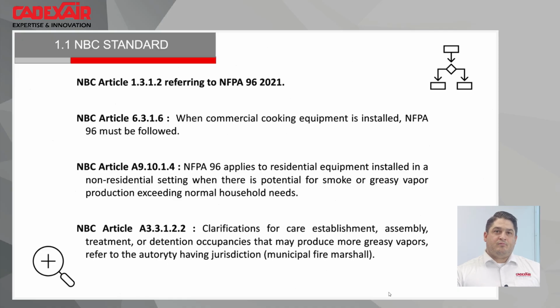The article after that, 6.3.1.6, is the one that mainly calls the NFPA 96. Everything has been put in, I will say, a little bit fewer words to be a little bit more compact for the PowerPoint. But in fact, as soon as you have commercial cooking equipment, you need to comply with NFPA 96. And after that, they put some more information: if you use residential cooking appliances outdoors or outside of the residential scope of work, and there's the probability of more smoke and grease than a normal household, you will need to comply with NFPA 96. There is also another qualification. If you have an establishment with assembly, treatment, or detention occupancy that could have more grease, they will also have a requirement for a fire protection system and NFPA 96 and everything.